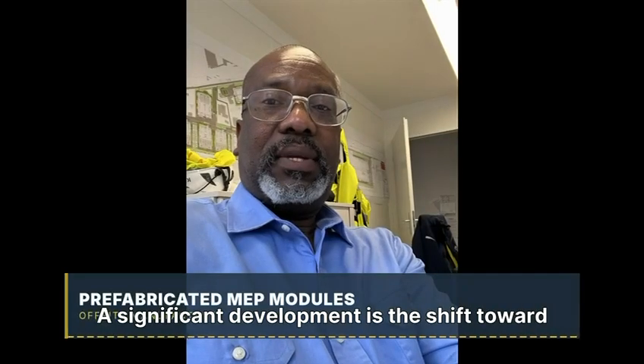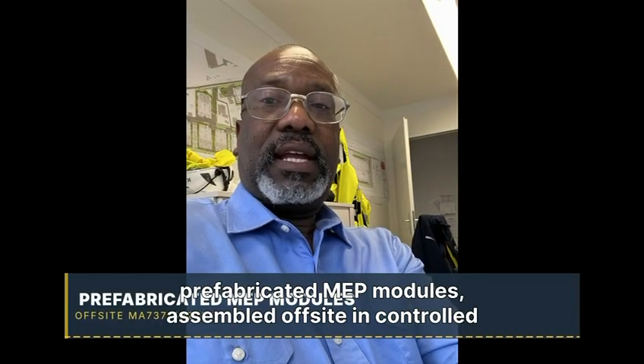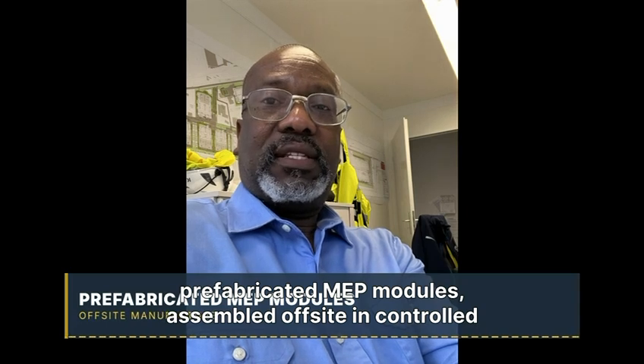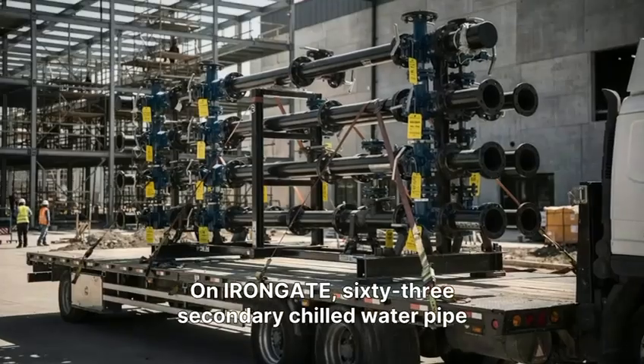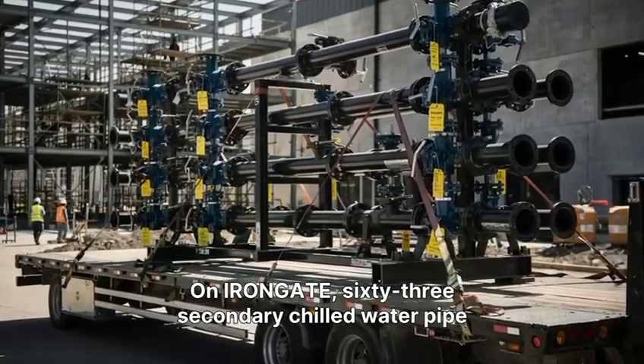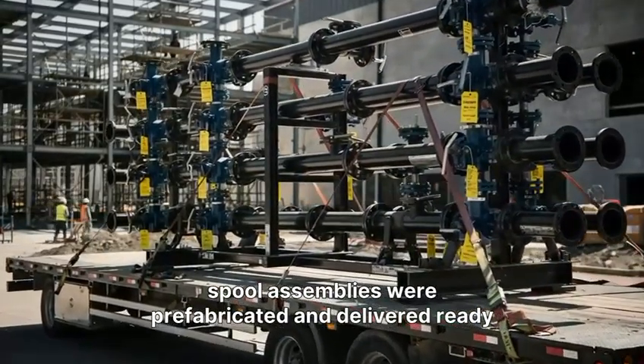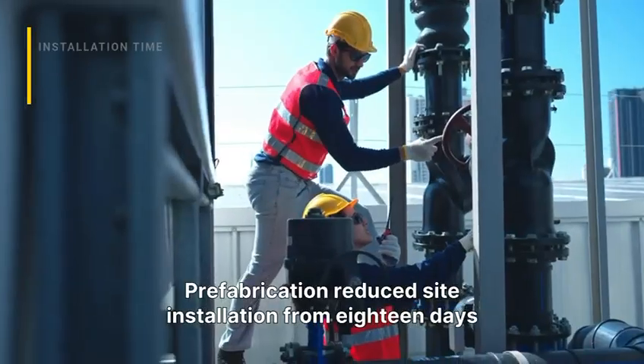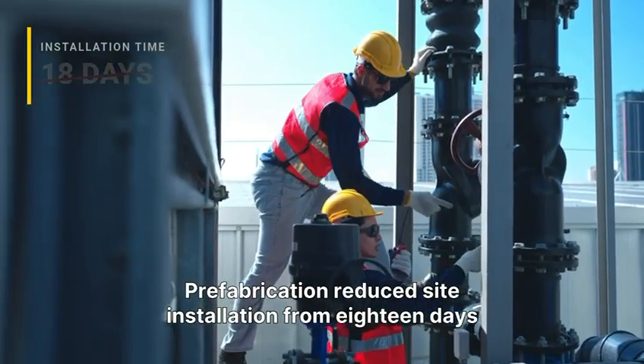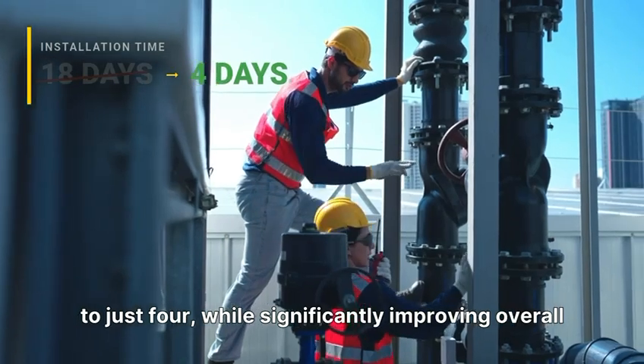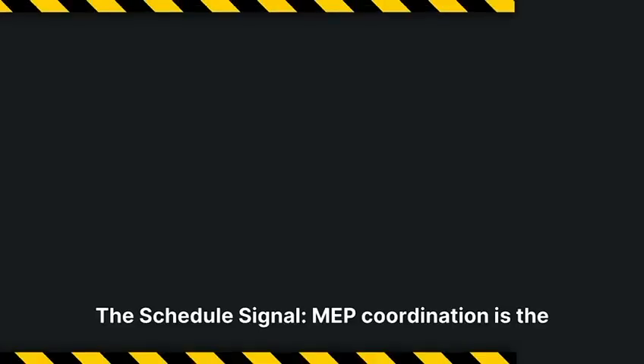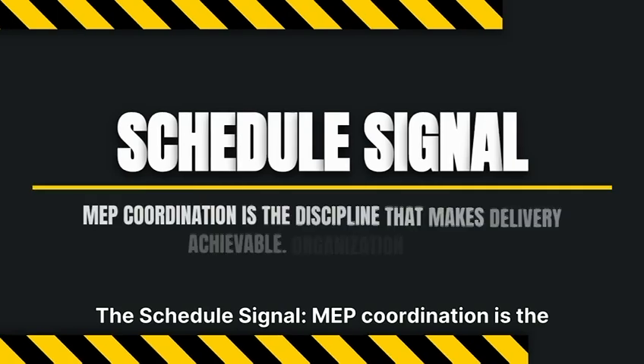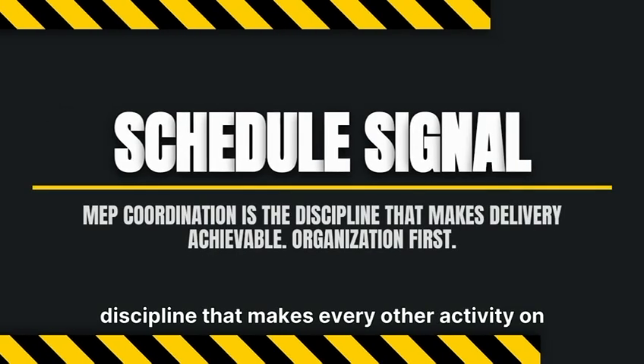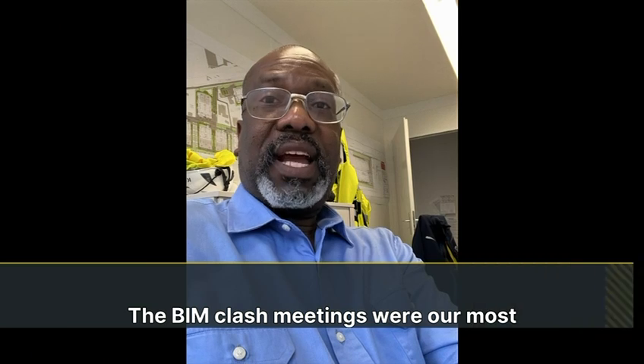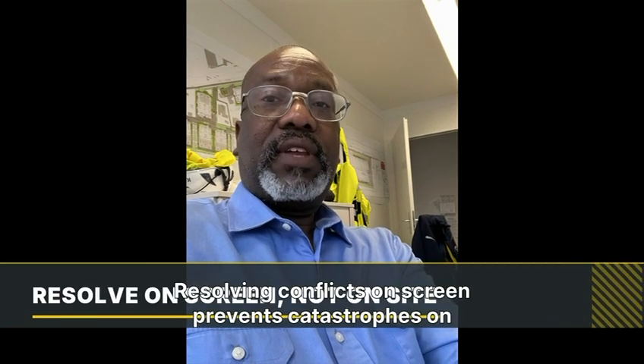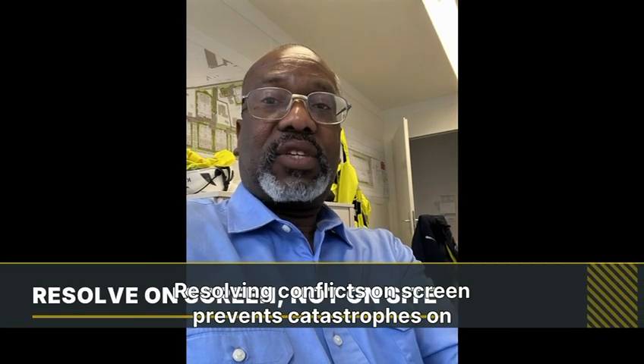A significant development is the shift toward prefabricated MEP modules, assembled off-site in controlled factory environments. On IRONGATE, 63 secondary chilled water pipe spool assemblies were prefabricated and delivered ready for lift. Prefabrication reduced site installation from 18 days to just 4, while significantly improving overall quality. The schedule signal. MEP coordination is the discipline that makes every other activity on the program achievable. The BIM clash meetings were our most important. Resolving conflicts on screen prevents catastrophes on site.